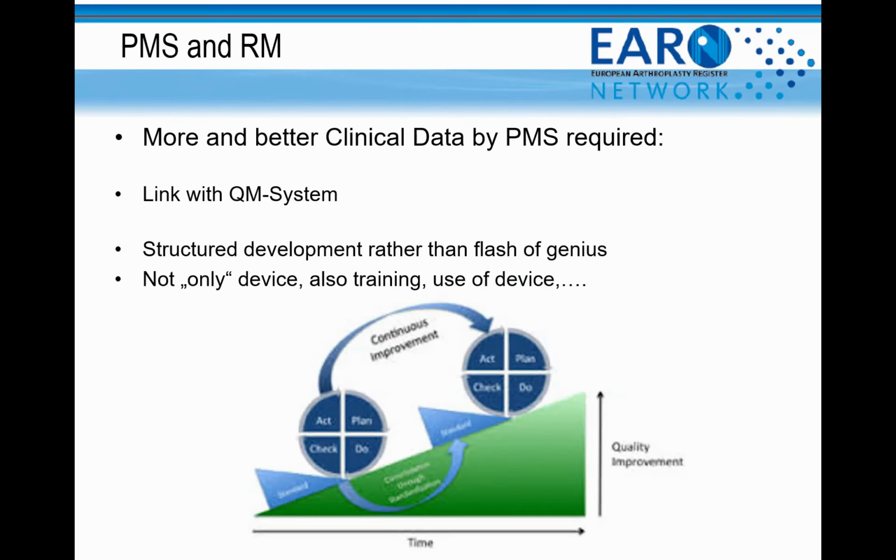Use of all clinical data applicable and robust evidence will allow building PMCF cycles for continuous improvement of the device and its use on the market. This can be executed via risk management processes and will provide evidence on process and decisions for inspection by notified bodies and other third parties.